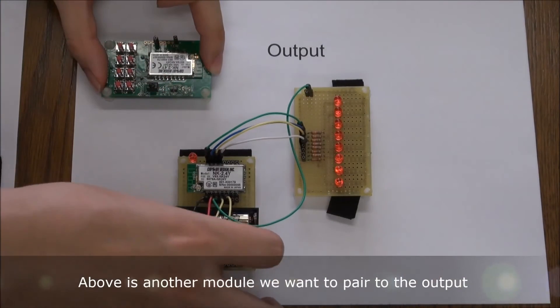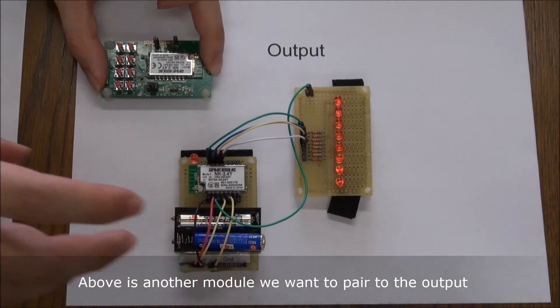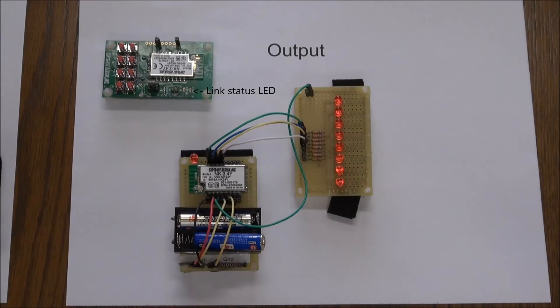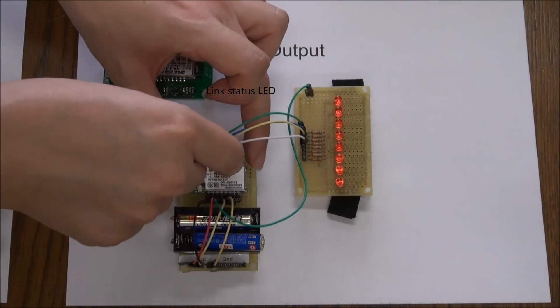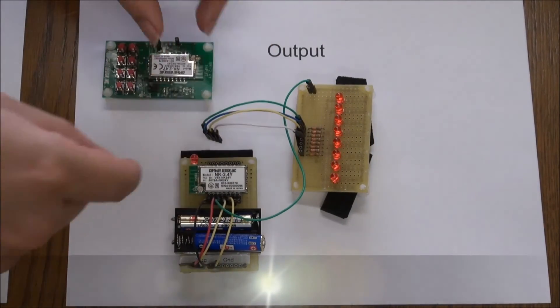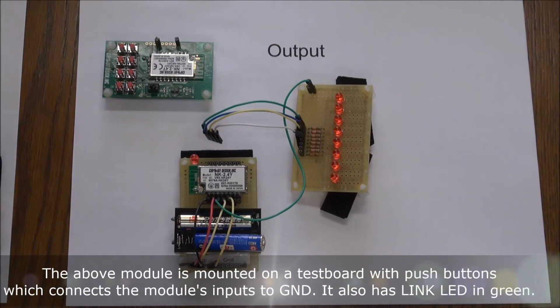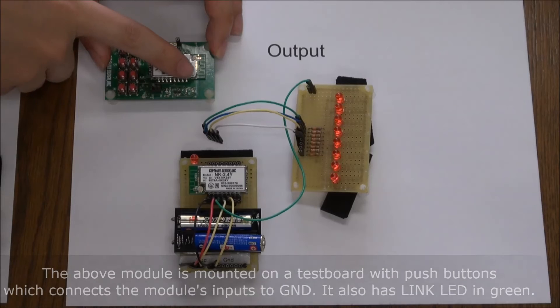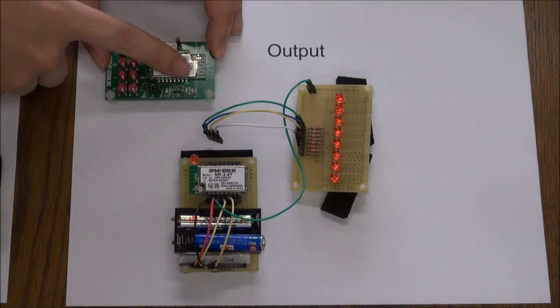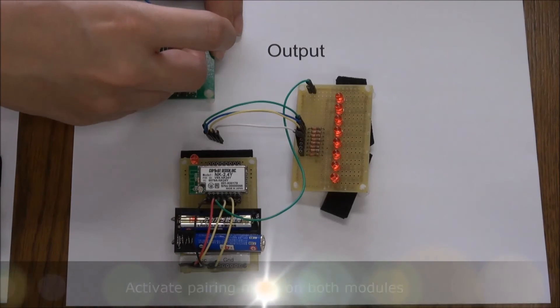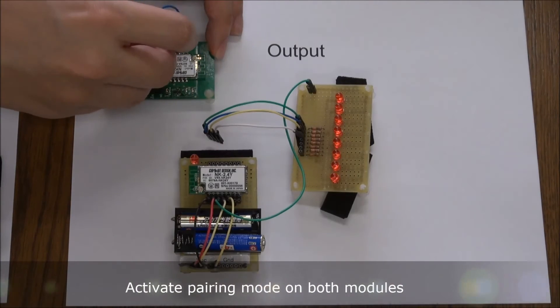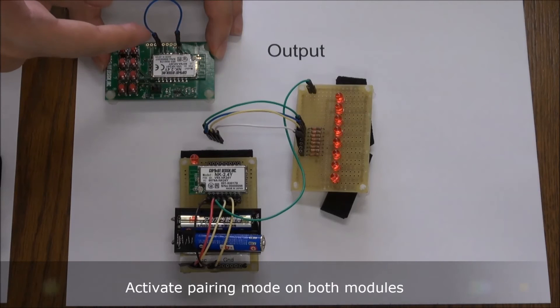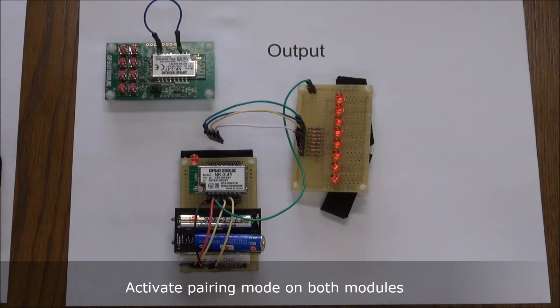I'll just switch everything off, and I need to disconnect my IOs. Then I need to connect the pairing mode terminal to ground on each of the modules, which I will do here. So now we've connected pairing mode terminal to ground. And I'll also do the same on here.